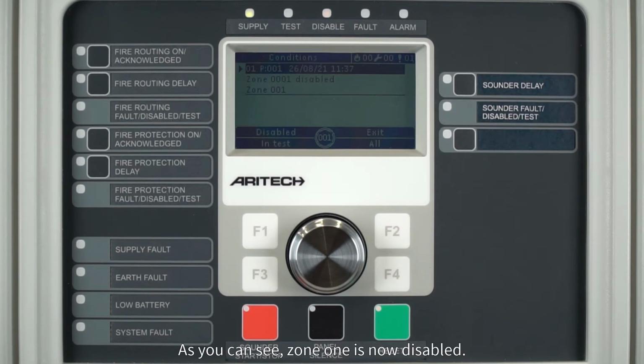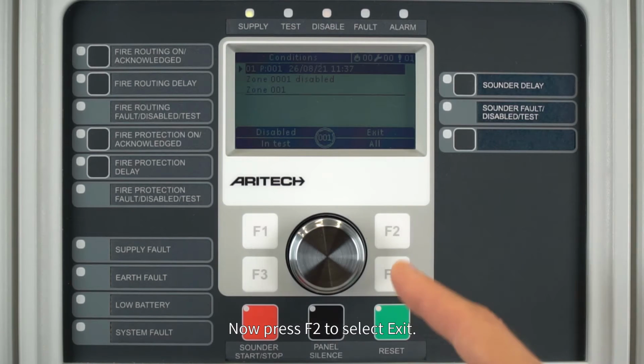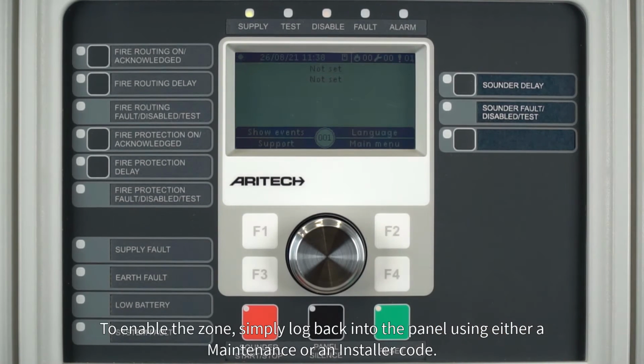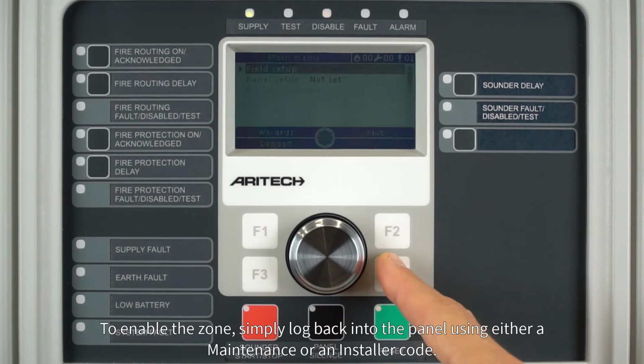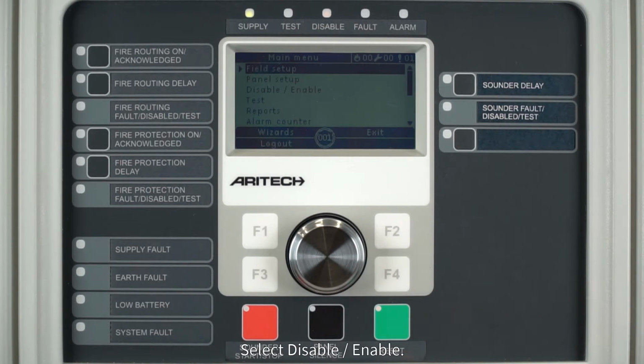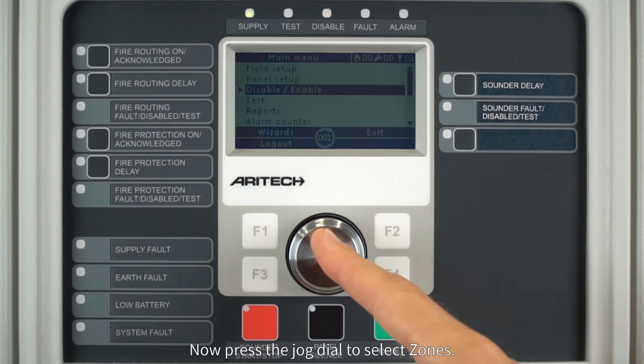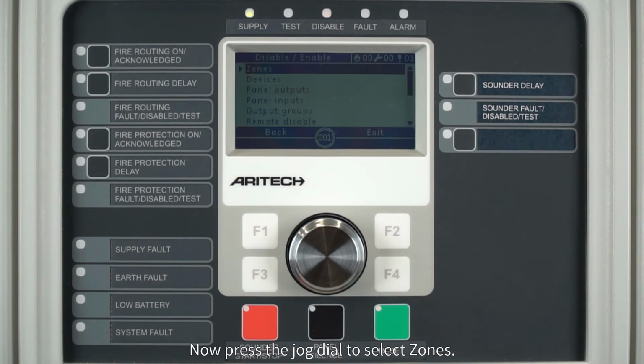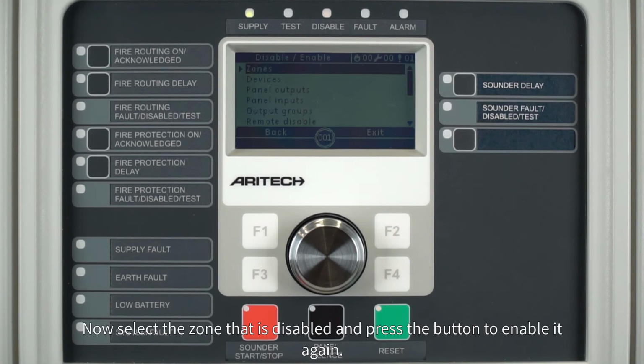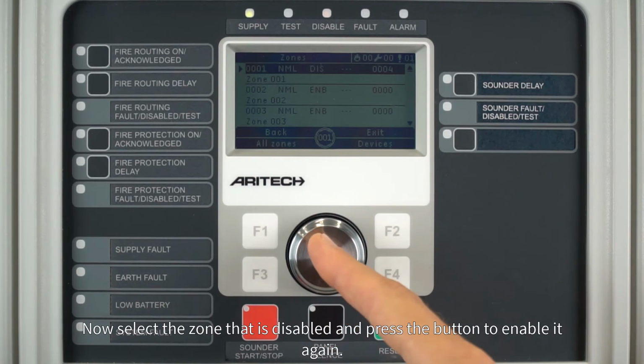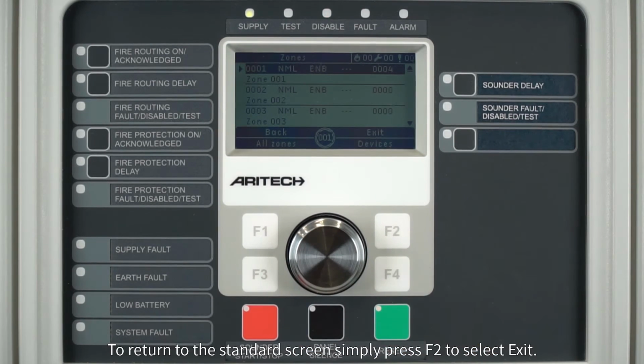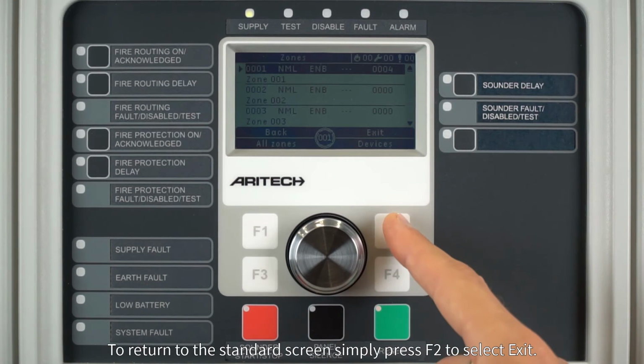As you can see, Zone 1 is now disabled. Now press F2 to select Exit. To enable the zone, simply log back into the panel using either a maintenance or an installer code. Select Disable Enable. Now press the jog dial to select zones. Now select the zone that is disabled and press the button to enable it again. To return to the standard screen, simply press F2 to select Exit.